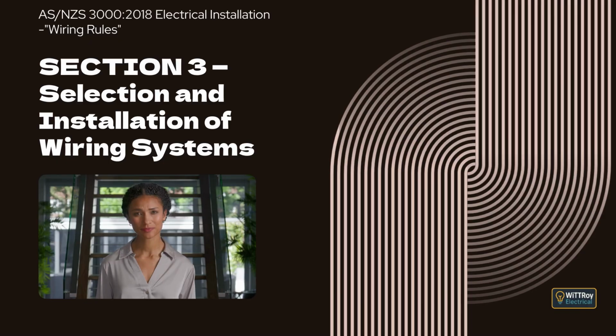The method used to join or connect conductors must suit the application and ensure the conductivity of the joint is not less than that of the conductor itself. All cables and conductors must be installed so that no undue mechanical stress is placed on any connection. Clause 3.7.2, Connection methods. This clause introduces the acceptable methods and requirements for connecting conductors. Clause 3.7.2.1, General.